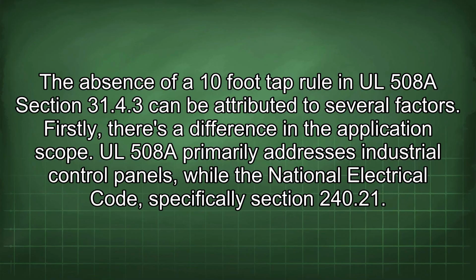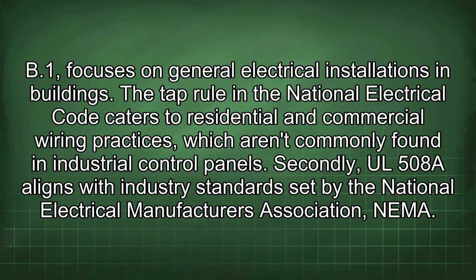The absence of a 10-foot tap rule in UL 508A Section 31.4.3 can be attributed to several factors. Firstly, there's a difference in the application scope. UL 508A primarily addresses industrial control panels, while the National Electrical Code, specifically section 240.21, B1, focuses on general electrical installations in buildings. The tap rule in the National Electrical Code caters to residential and commercial wiring practices, which aren't commonly found in industrial control panels.